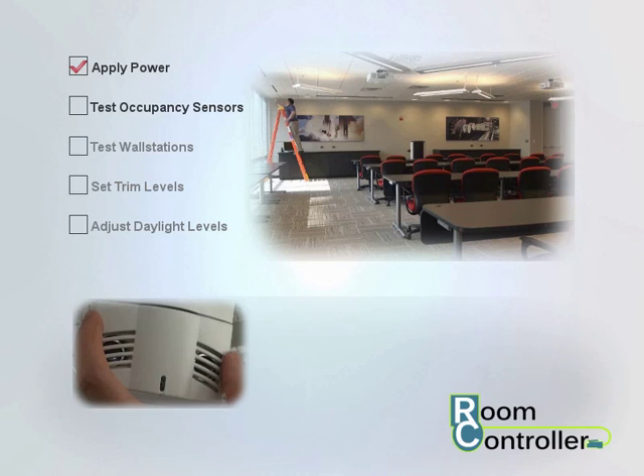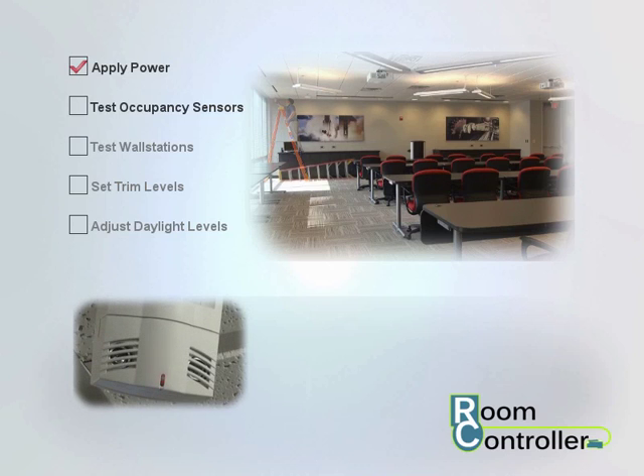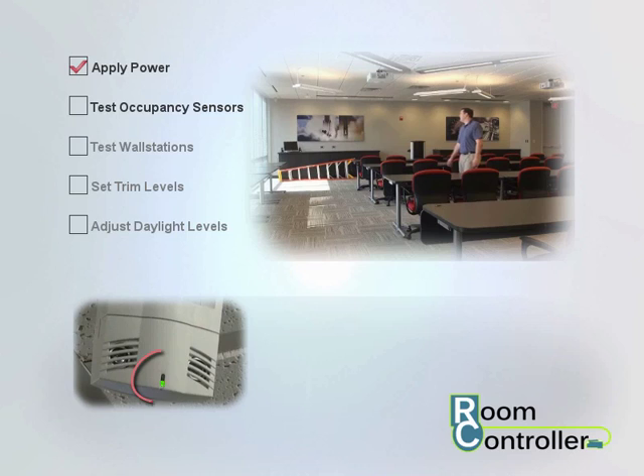During test mode, the sensor will have a shorter 15 second time delay and the LEDs will flash rapidly when motion is detected. Move around the controlled area, verifying that the occupancy sensor LEDs flash with each motion and stop flashing when you stand still.